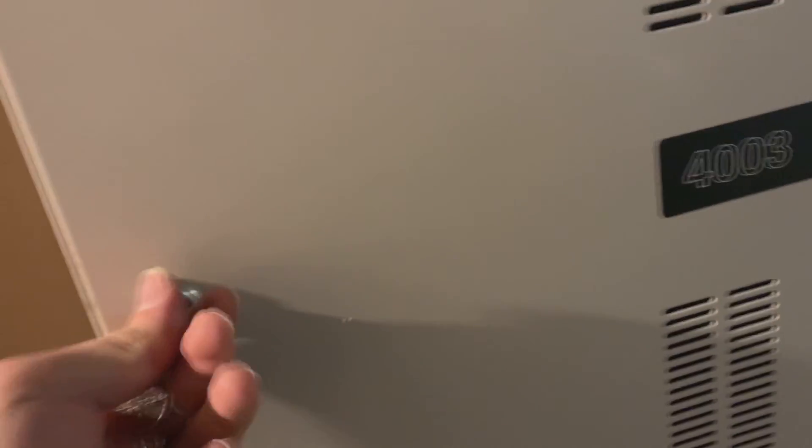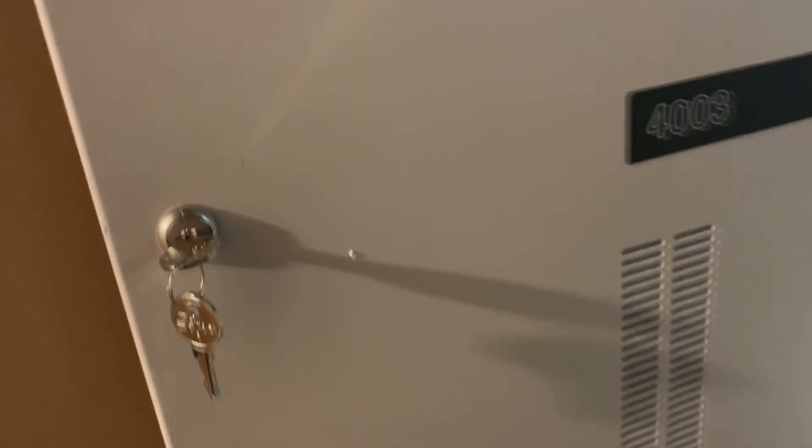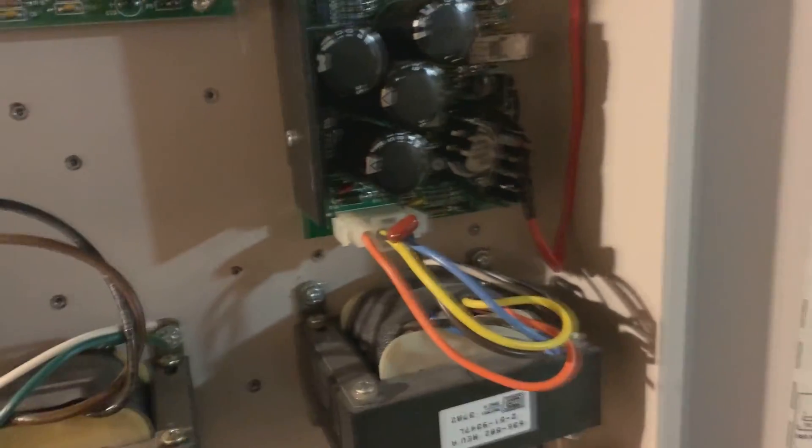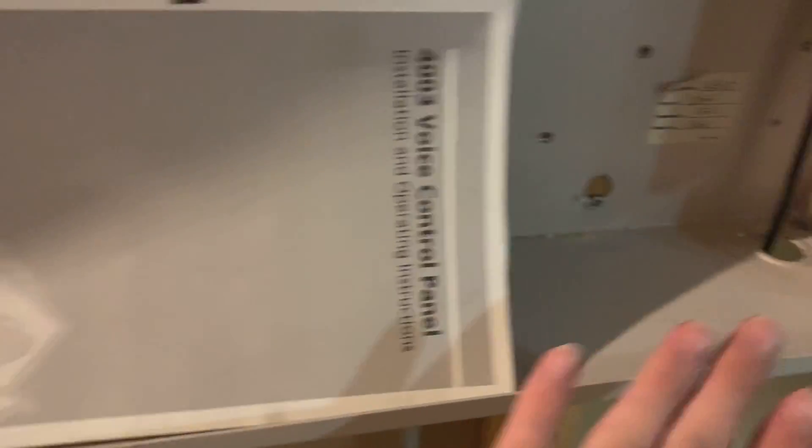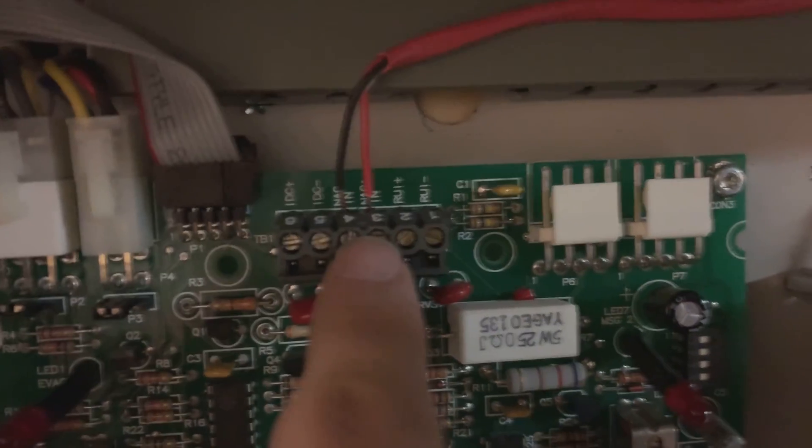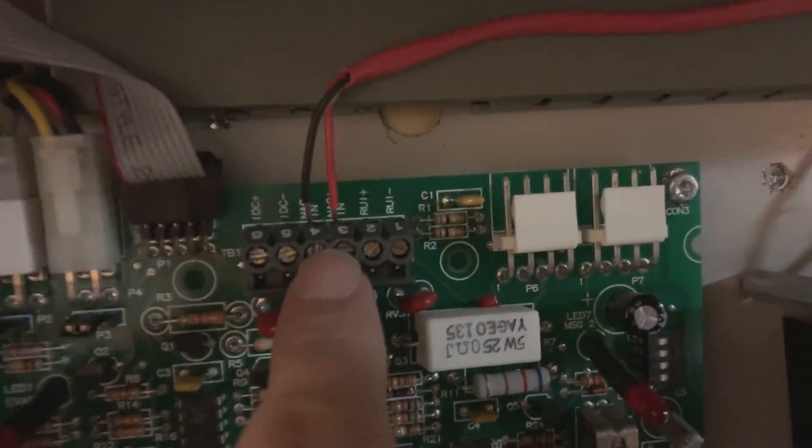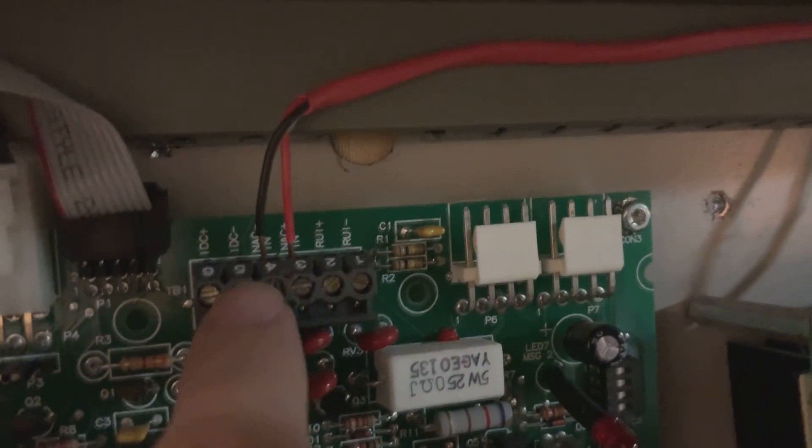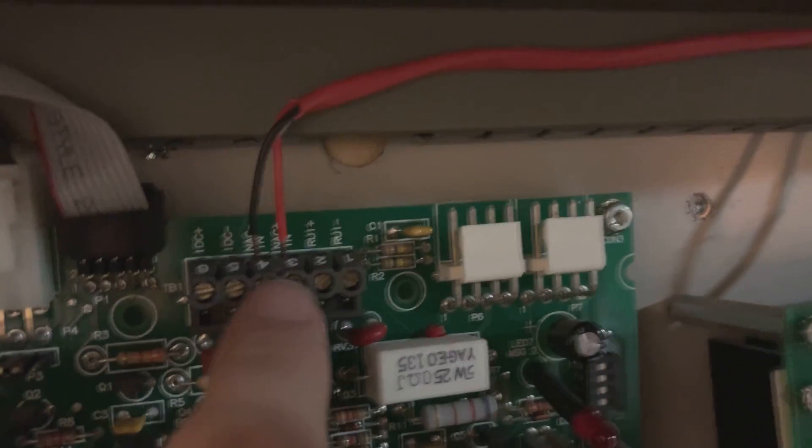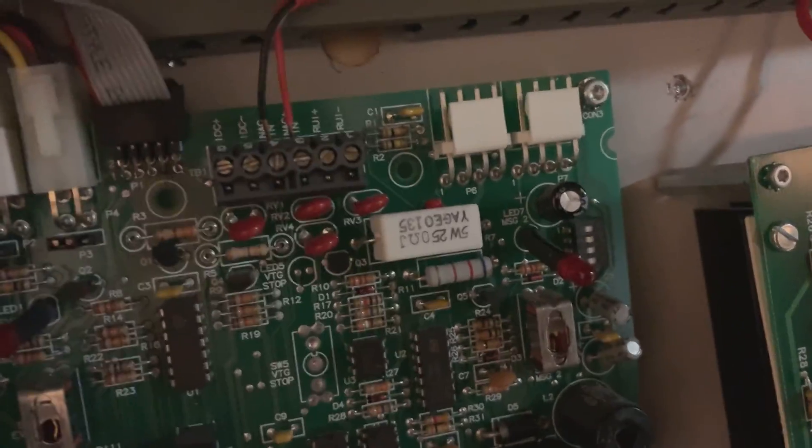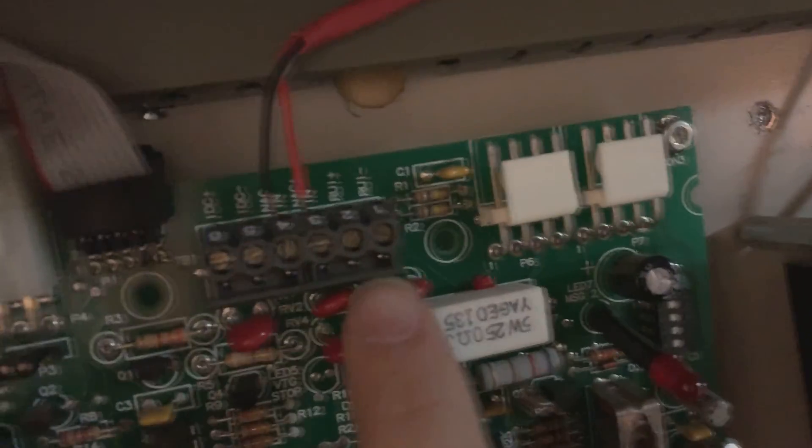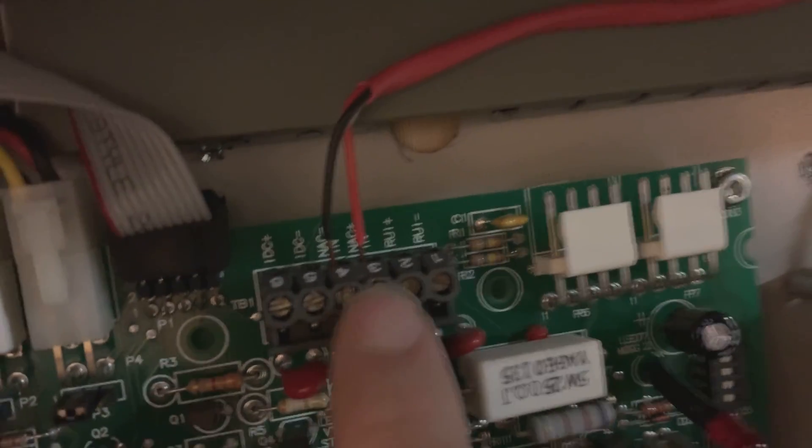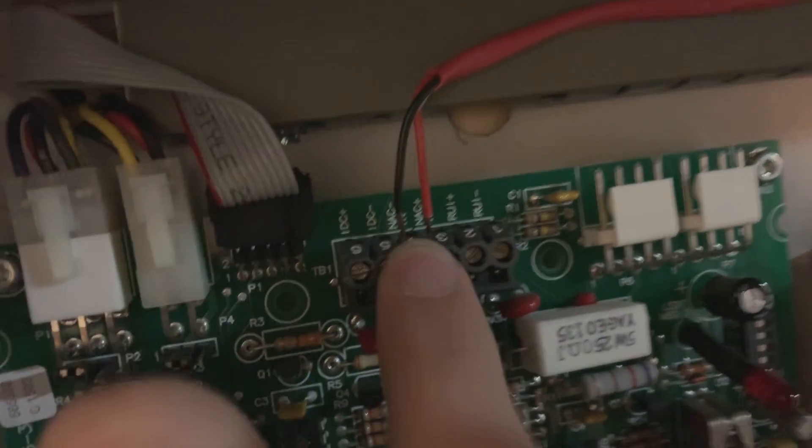If you want to see how that's wired up, let's take a look at that. Let's go over the wiring of this thing real quick because it's tedious. I don't have any batteries in here. I don't actually even have the battery or this panel supervised by the 4010 right now. The 4010 just says it's normal. Right now we have these guys coming in here. If there's trouble it'll actually cause an open circuit. Of course I've bypassed this to keep the system normal while I don't have a set of batteries in here. The resistor would normally go here between these two. This is coming in from the 4010.